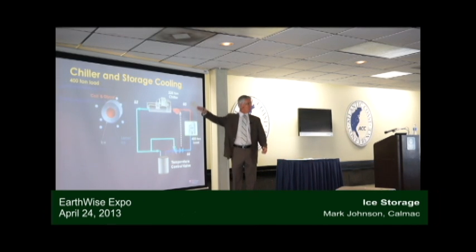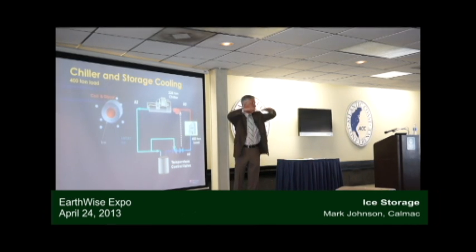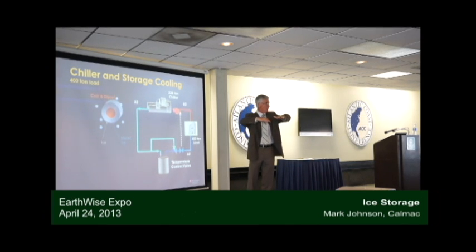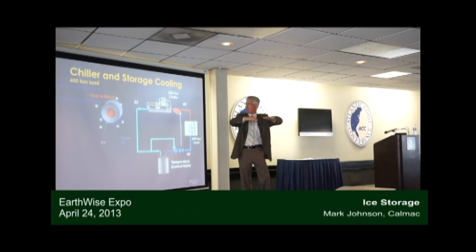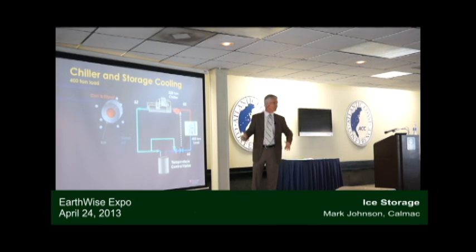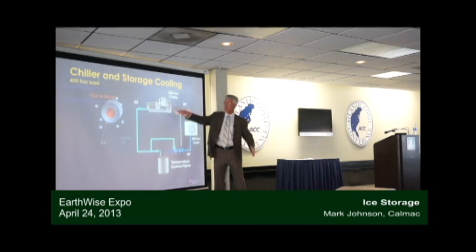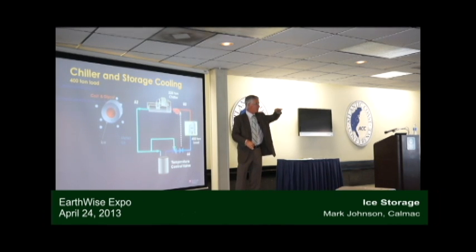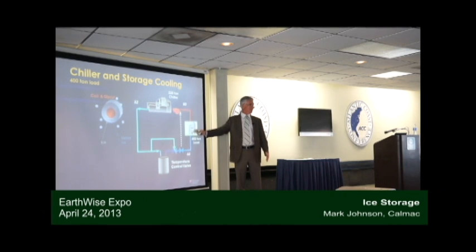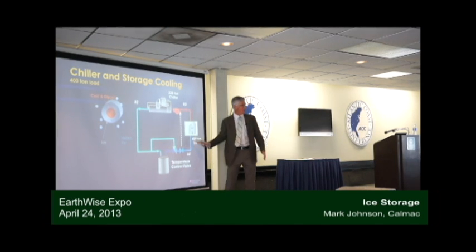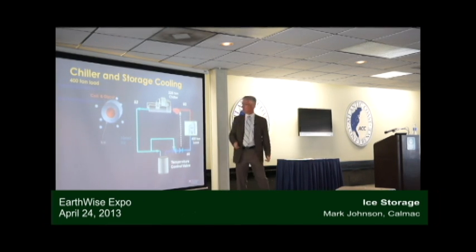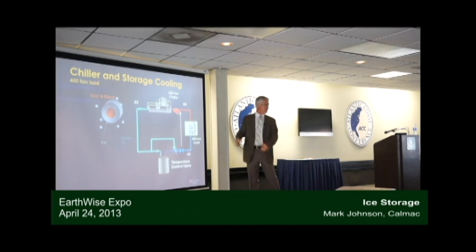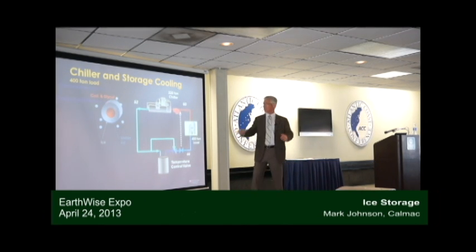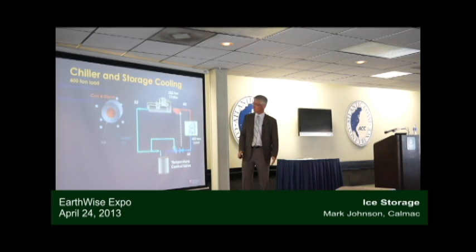The goal of an ice storage system is to flatten the load. It's to flatten the kW that the utility sees. You bring that chiller up to 220 and it's running at a nice flat load. What's the peak? 400. I'm going to let the ice get the peak. All right? This is a partial storage facility. So partial means chiller first, ice second.